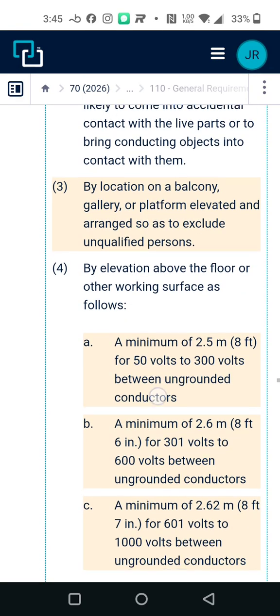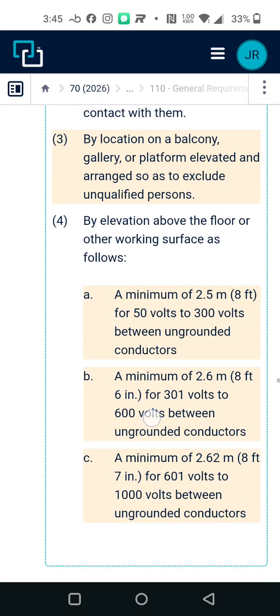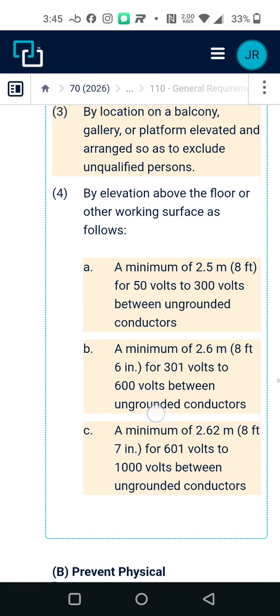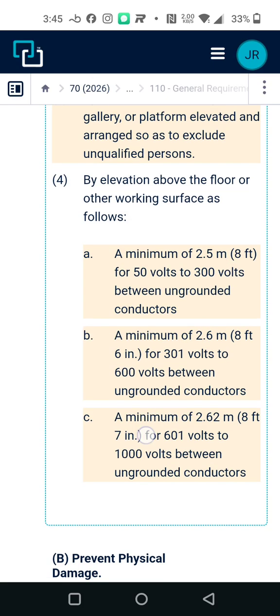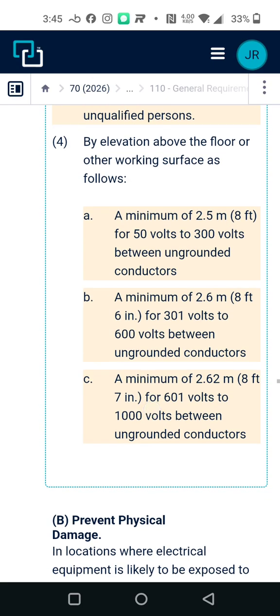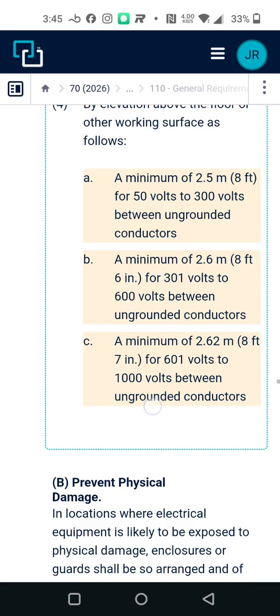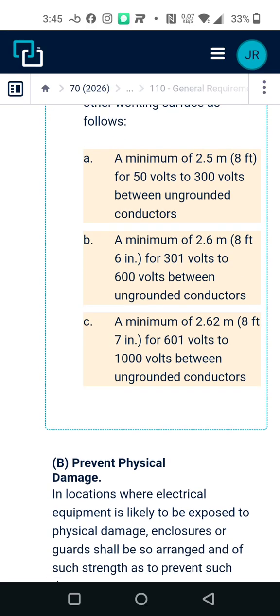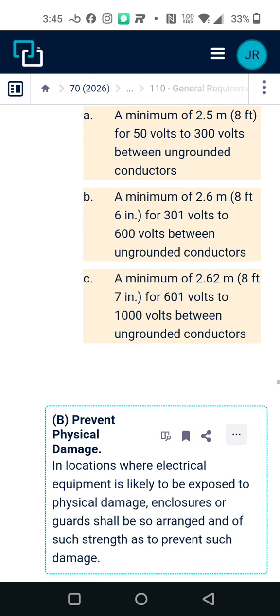By elevation above the floor or other working surface as follows: a minimum of 8 feet for 50 volts to 300 volts, a minimum of 8 feet 6 inches for 301 volts to 600 volts, and a minimum of 2.62 meters or 8 feet 7 inches for 601 volts to 1000 volts between ungrounded conductors.